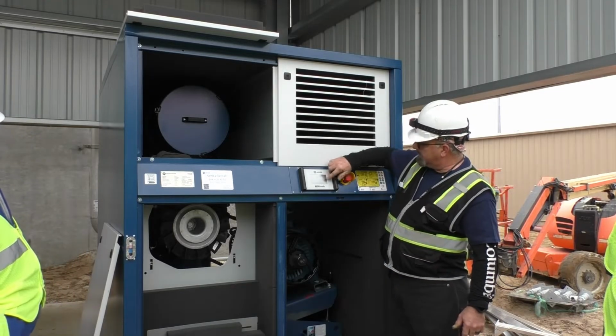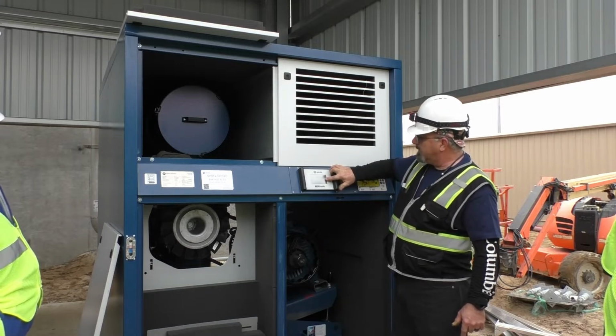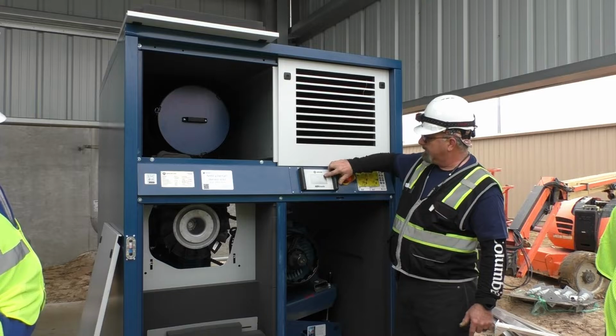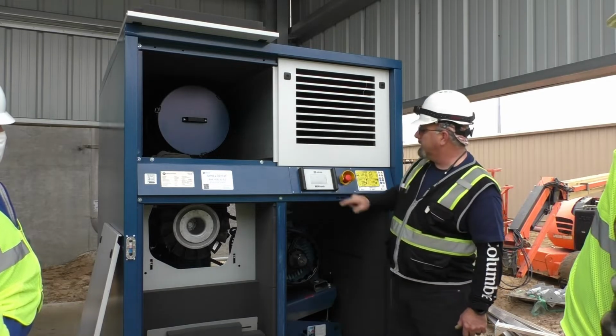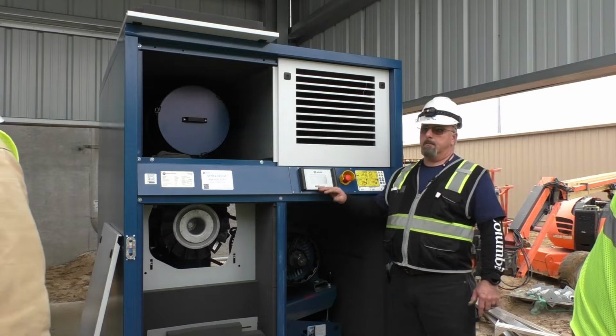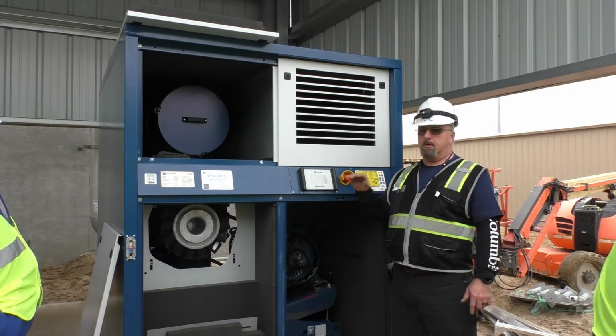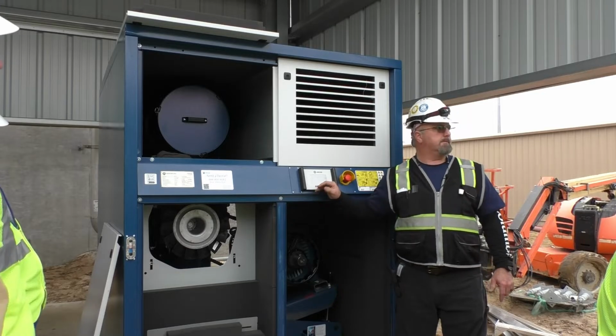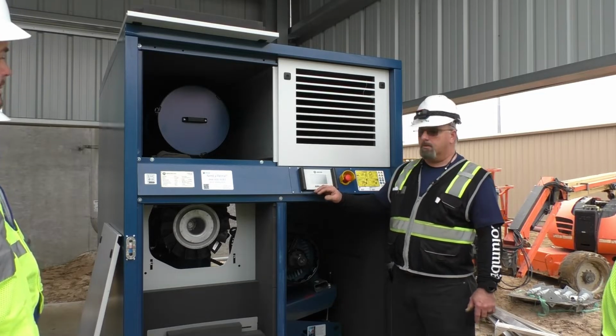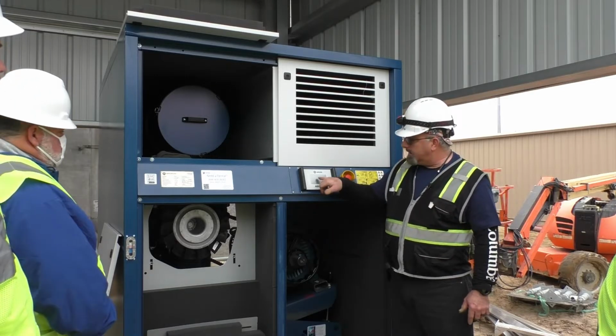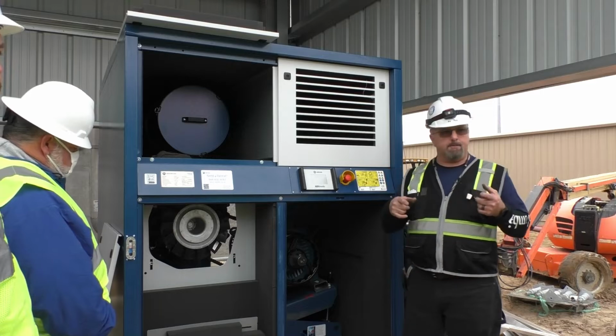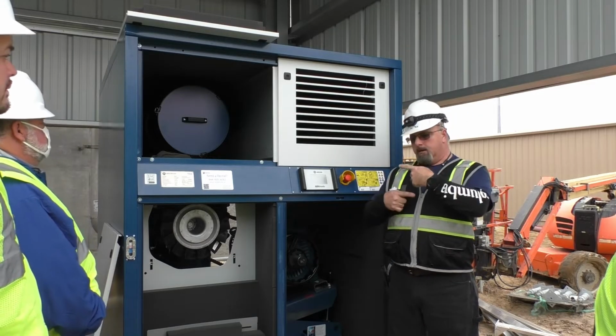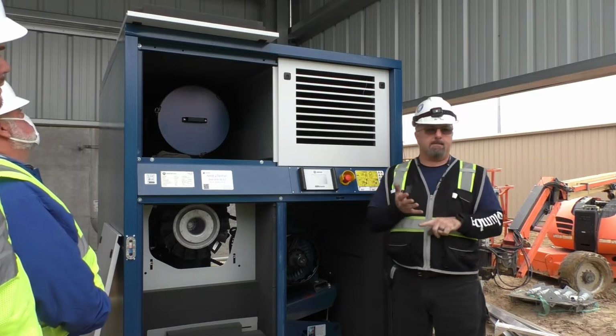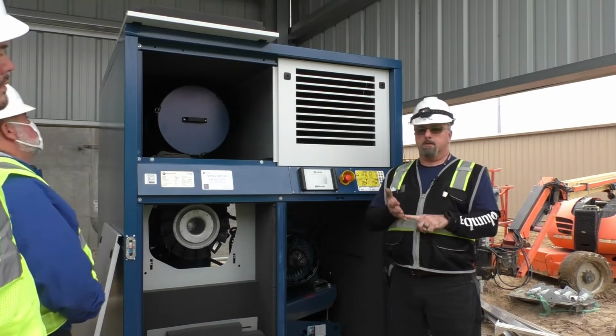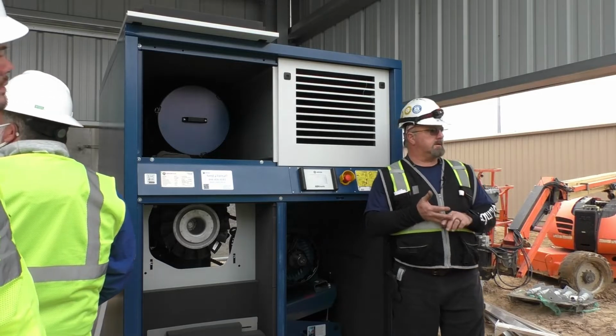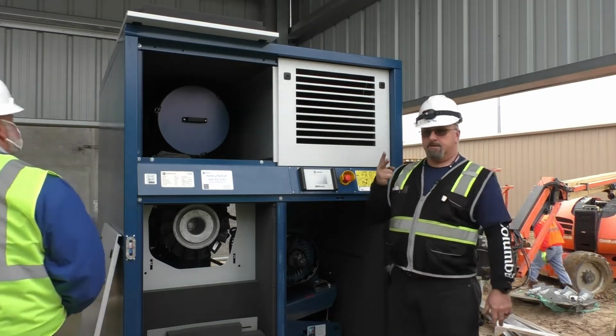And to get out of the screen or to scroll up and down to the different menu items, you just hit the up or down button. The X is out. Fault registry. I don't think it's infinite, but there is a long list. You will probably never fill up this fault registry list. That's how much data it can record. As you're looking at the screen, there will be 2 items for each alarm. One points to the right, and one points to the left. One is the snapshot it took when it shut down. The other is the snapshot it took once the machine came to a stop and the run command was removed. So that's your 2 items.